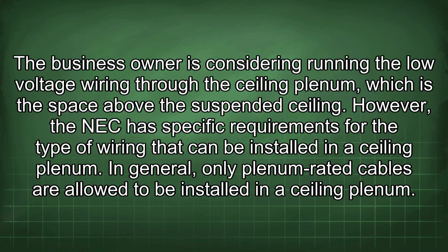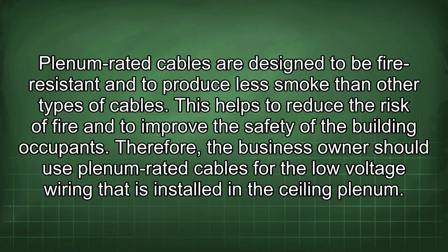In general, only plenum-rated cables are allowed to be installed in a ceiling plenum. Plenum-rated cables are designed to be fire-resistant and to produce less smoke than other types of cables. This helps to reduce the risk of fire and to improve the safety of the building occupants. Therefore, the business owner should use plenum-rated cables for the low-voltage wiring that is installed in the ceiling plenum.